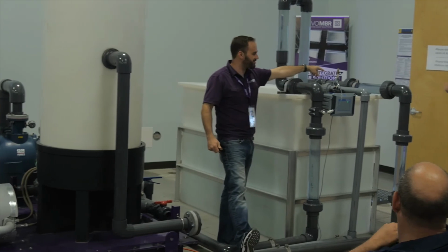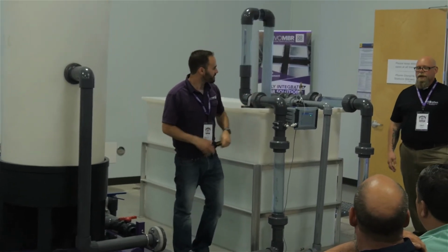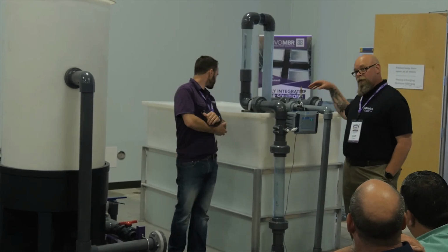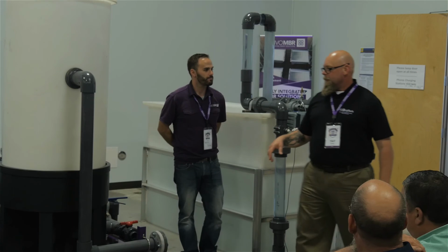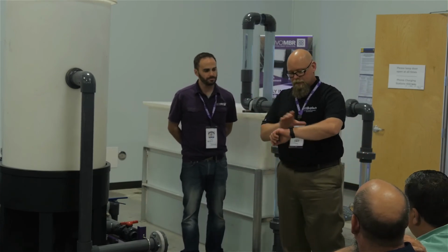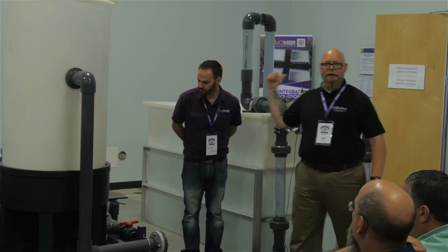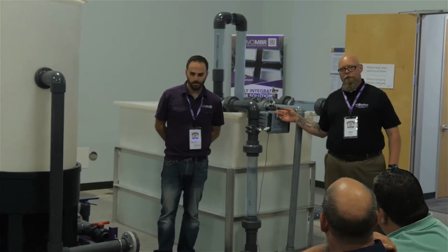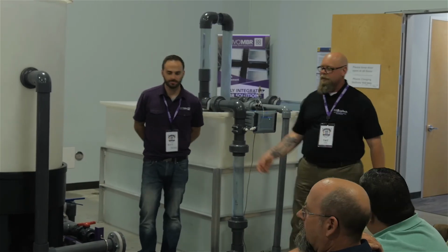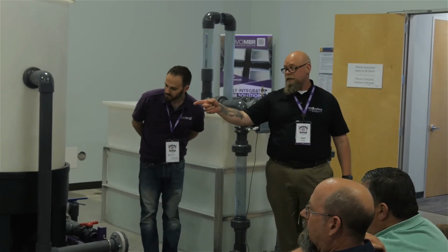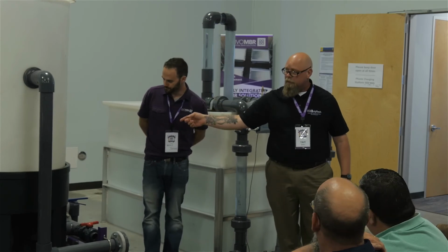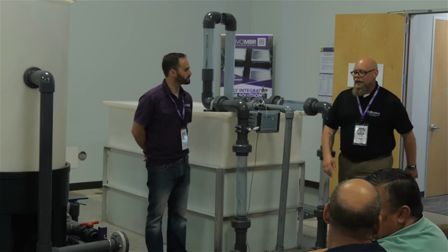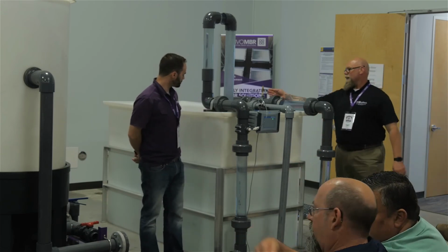Okay, it's a simple setup for demonstration purposes. There is a membrane in here, and we've got air on the membrane, so I've got a screen. We're pulling out of this tank and through the pump right back into the tank. In the inline instrumentation, turbidimeter right before we go back to the tank. Pressure transducer, we are calculating TMP. And a mag meter, flow meter for the permeate flow. And not instrumentation, but we've added a small valve with a 1/16 orifice on it.